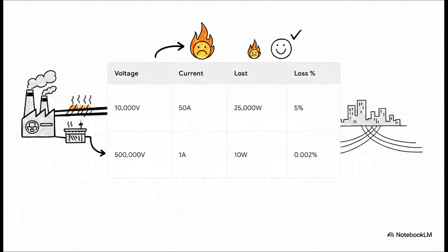Let's run a quick, jaw-dropping comparison. Imagine a power plant trying to send 500,000 watts of power over lines with 10 ohms of resistance. If we send it at 10,000 volts, we'd need 50 amps of current. 50 squared is 2,500, times 10 means we lose 25,000 watts as pure, useless heat. That's a 5% loss right off the top.